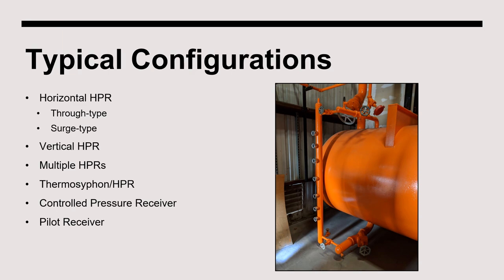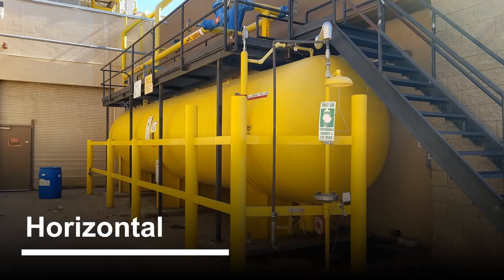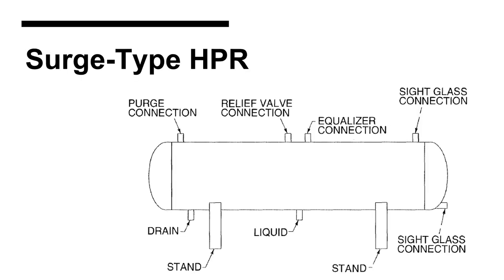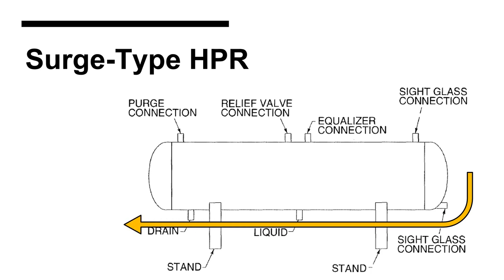There are many ways that a high pressure receiver can be configured. Often, high pressure receivers have a horizontal orientation. Horizontal receivers can be configured as through type, which means that liquid from the condenser flows through the vessel before being supplied out into the system. Alternatively, high pressure receivers can be arranged as surge type receivers. When this is the case, ammonia draining from the condensers is piped directly to the system, and ammonia will only surge into the vessel if all system loads are satisfied.